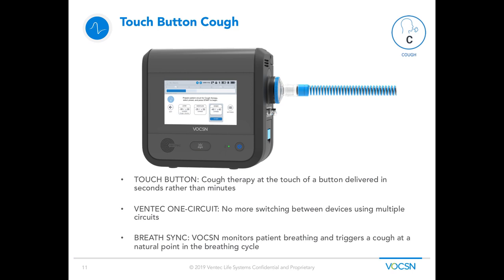I would simply hit start, and VOCSN would go from ventilating the patient. It would pick a natural point in the patient's breath, again, because it's one system and it's breathing for the patient, as well as then providing the cough, so it knows exactly when the comfortable point in the breath is to provide that cough. It then would do the cough. Maybe you do three cough cycles, so an insufflation, exsufflation, repeat that three times, bring those secretions up and out of the airway, and then go right back to ventilation. So uninterrupted ventilation.